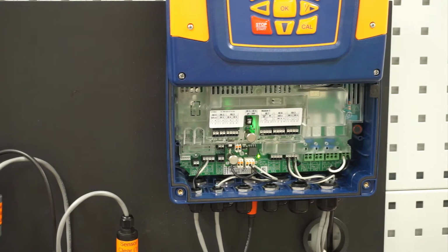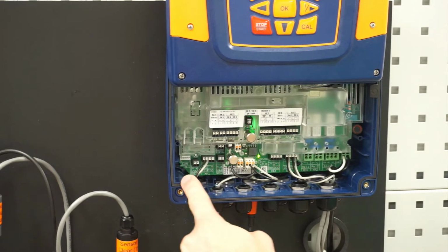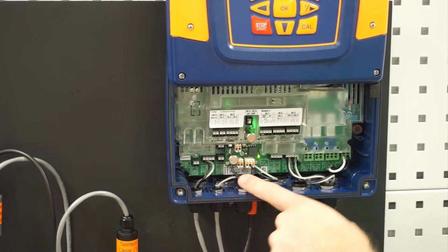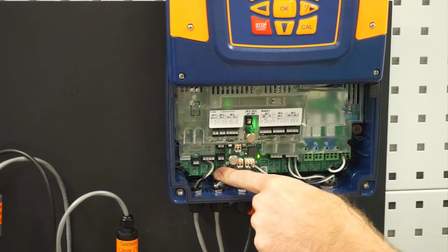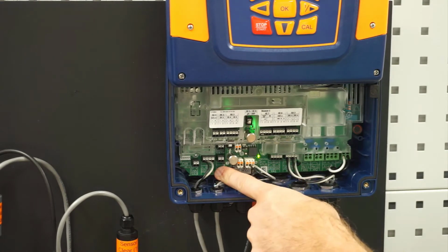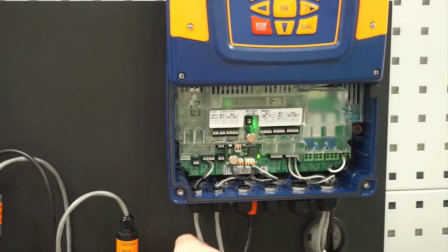First, I want to walk you through what sensors and what wires we landed here from the factory, and then we'll backtrack and show you what all the other open slots are used for. The first wire we come into right here is landed into DI1. That is a digital input. That wire we can trace back, and that goes to our flow cell. So that is our flow sensor.